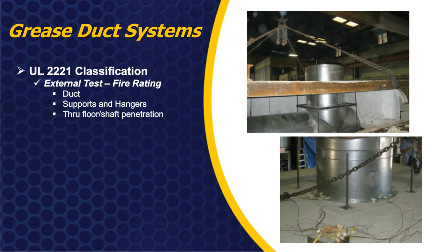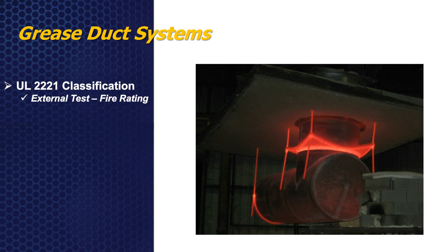Once a product is assembled, it's going to sit in the oven, and it's going to be subject to temperatures to simulate a grease duct fire while the duct is being pressurized to make sure that it can maintain a certain level of pressure and stay structurally intact with the temperatures that it's being subjected to. And then once you've passed that section of the test, the test unit is going to be lifted out of the oven, and it's going to go through a spray test or a fire hose test where they're going to blast the ductwork and the support structure with the fire hose to make sure that it stays structurally intact to the concrete floor in the event that the fire department is in there putting out the fire. So it's a very, very strict and very difficult test to pass.